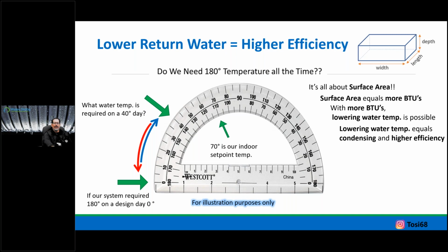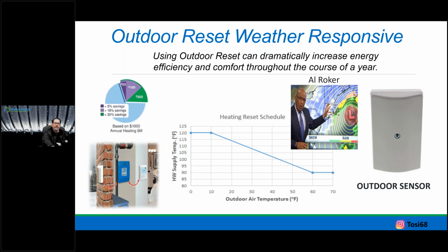So here is just showing you how we now have the ability, not to modulate, right, but just to end the switch, the signal to the boiler operating controller, aquastat if you want to call it that, okay? So I had this device, an outdoor sensor, call it Al Roker, right? That's giving a microprocessor, which is now controlling the signal from, let's say, a switching relay. Instead of going directly from the switching relay to the boiler, there might be this microprocessor in between. And this is seeing outdoor temperature. It has a sensor that's seeing maybe return water temperature, I think, or supply water temperature, I forget which.